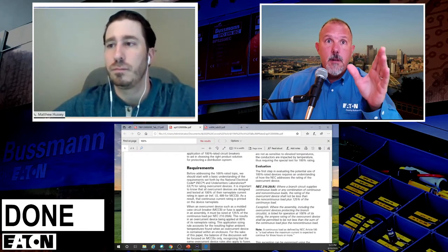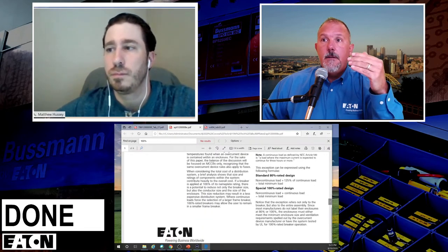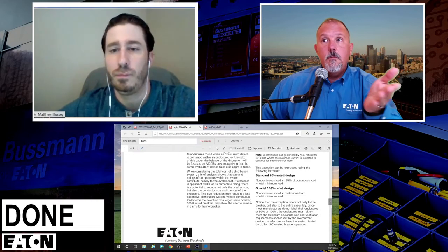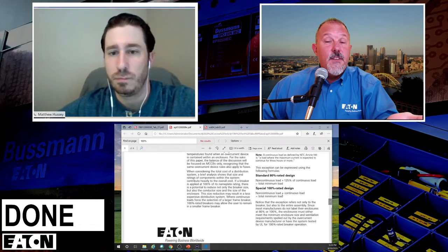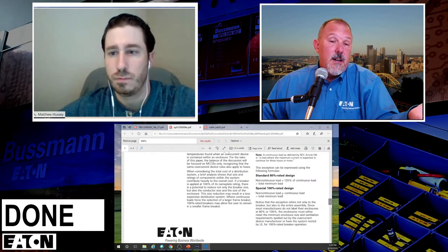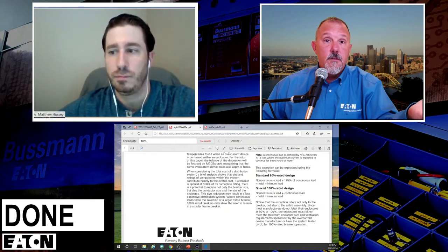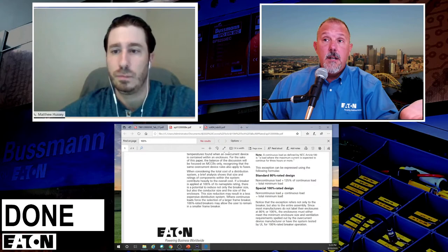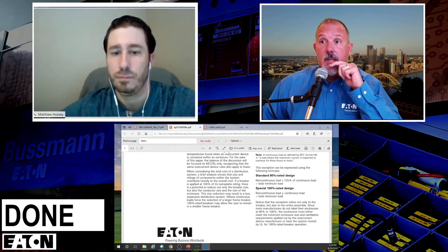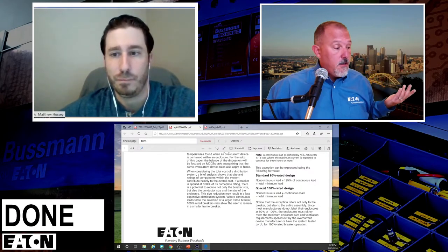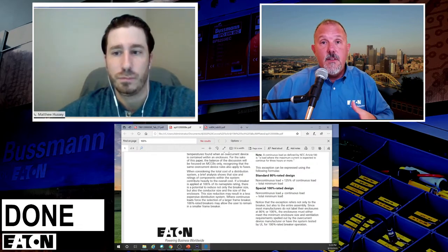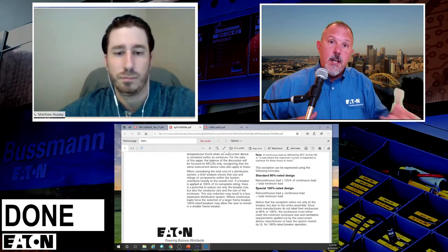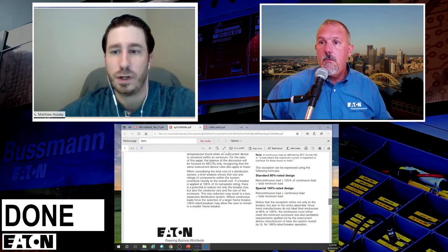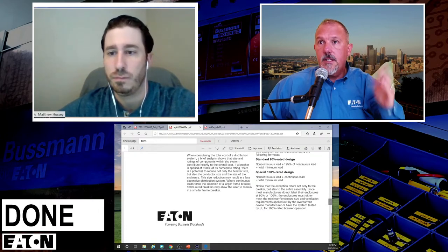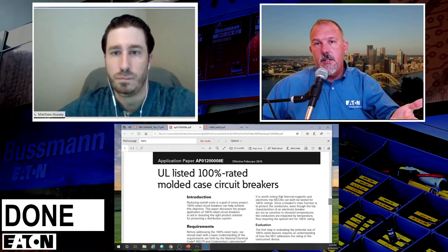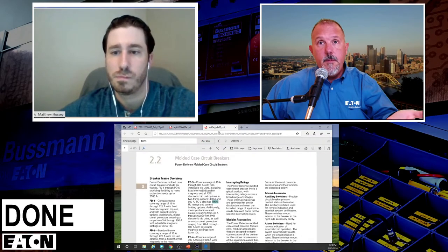But this document here really helps. It goes over exactly what we just said, talks about the 100% rated, doing the load calculations, and the non-continuous load plus 125%. If I don't have any continuous loads, then I'm using my breaker to serve the load. 100 amps is 100 amps. It's only when I have continuous loads that I have to worry about that. And that's because of the heat, right? Right, I'm not giving it time to cool down, shutting loads on and off. Correct. And the main message here is make sure that the equipment is rated correctly.